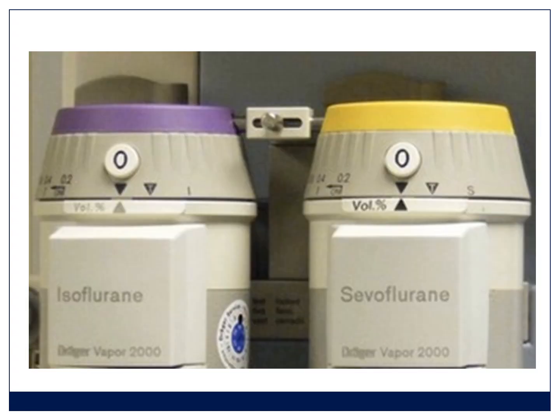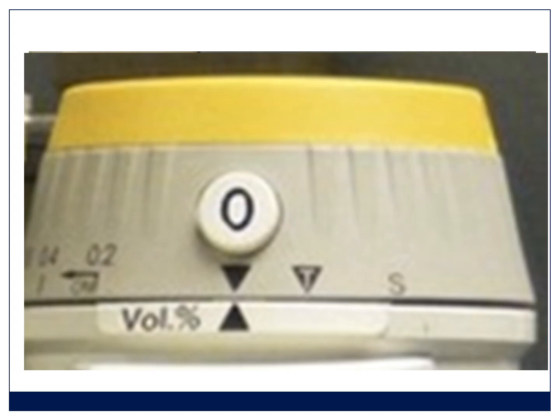Normally you've got 2 vaporizers. Make sure that they're filled, at least half full with the correct agent, and they're ready to use. You test something called the interlock mechanism, which means you turn one on and then make sure the other one is not able to be opened. So they actually prevent you administering 2 agents at the same time. And you'll see on the front of these things, the 2 triangles are lining up there. That's the neutral position. And just to the right of the screen, there's a little T there. And if you want to transport it, you have to move the marker to the T, which allows you to travel. And that's basically what that is for. So those should be checked.